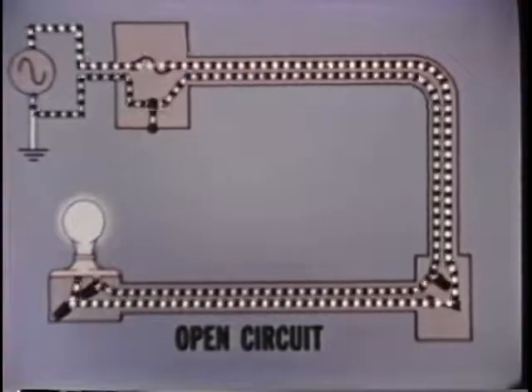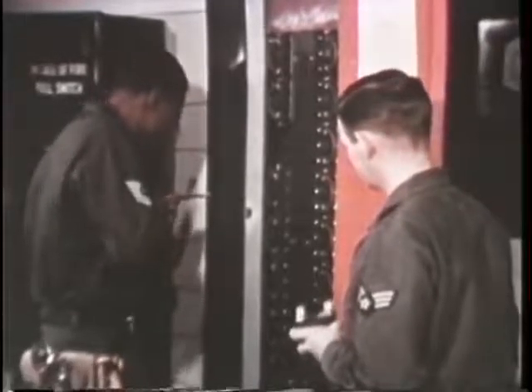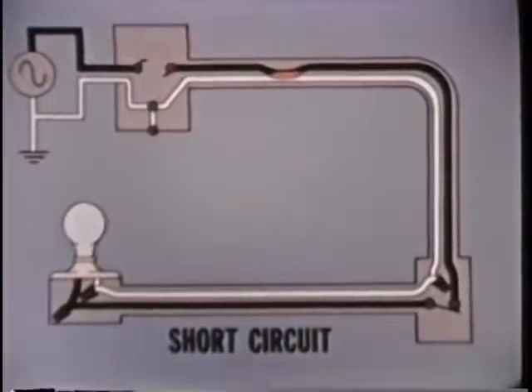The fuse or circuit breaker normally does not react to an open circuit. In the field, electric circuits are generally installed in a manner that rules out a visual inspection of the wiring itself. However, to be able to correct any trouble, the electrician must be able to identify the type of malfunction that exists in the line. The correct tools and equipment will make this identification easier. The tools normally used for troubleshooting are a voltage tester and a multimeter or buzzer type continuity tester.